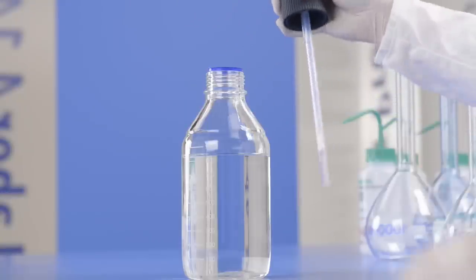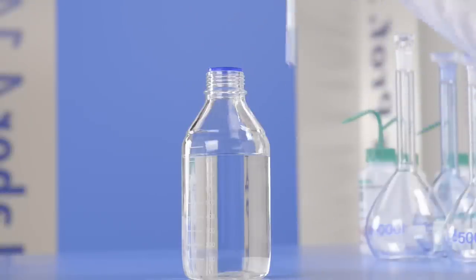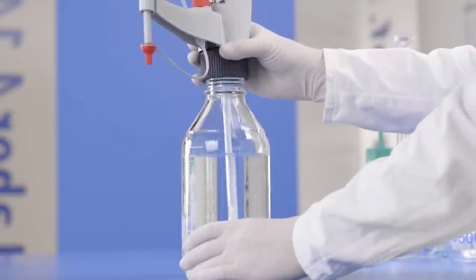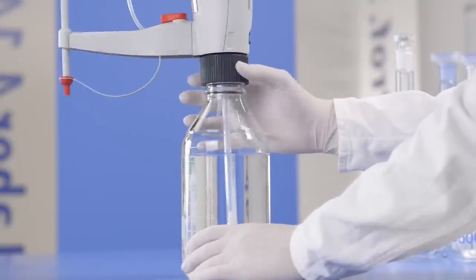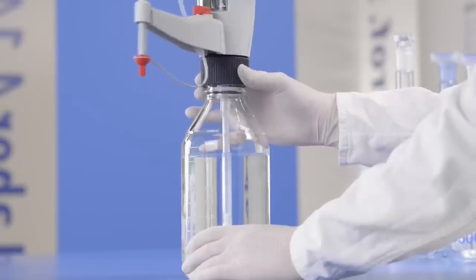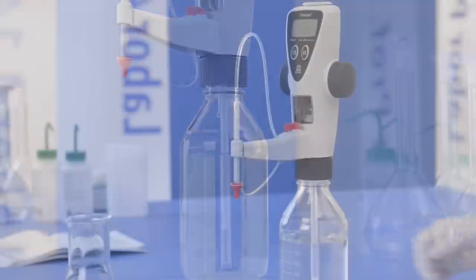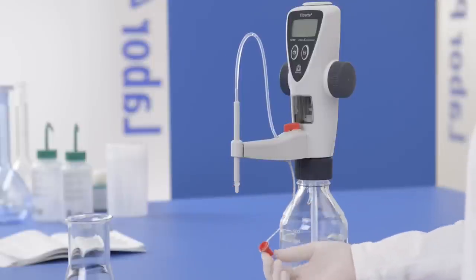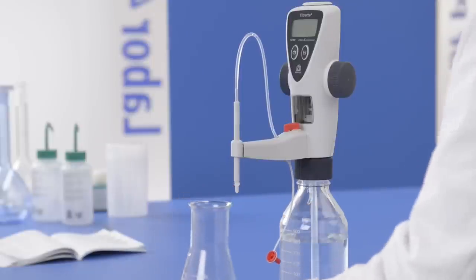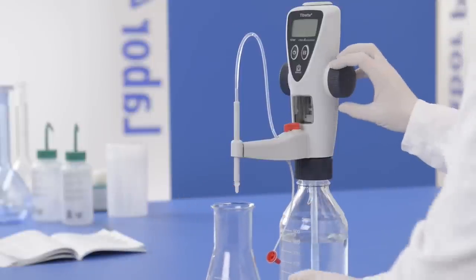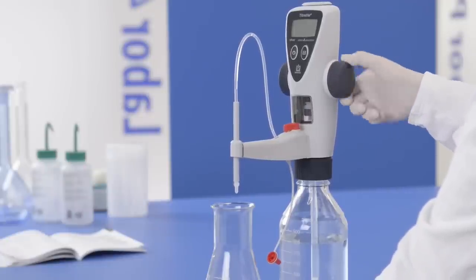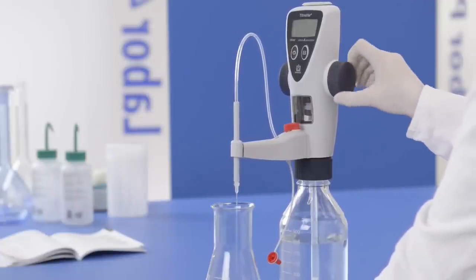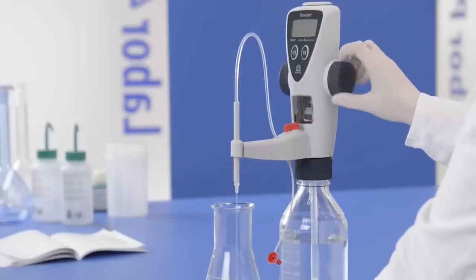After mounting the Titrette onto the titrant bottle, adjust the titrating tube. The titrating tube may still contain residual test liquid. To remove it, fill the dispensing cylinder once and empty it with the red valve set to titrate.